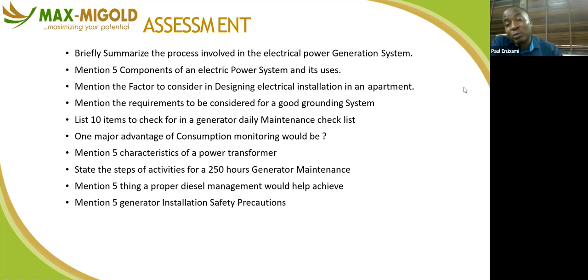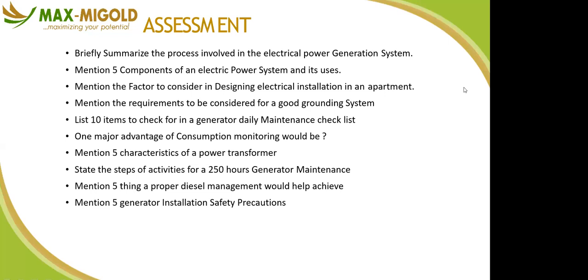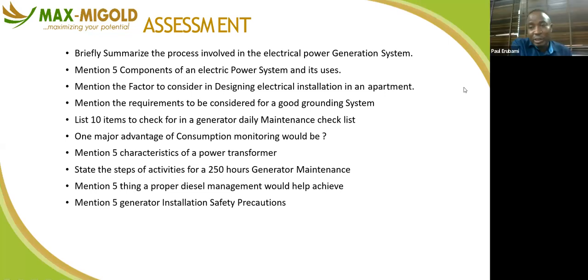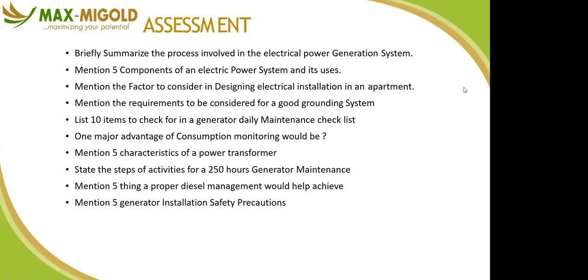There are other facilities that you are not putting to use, maybe your conference room or some AC or some room. So when you are doing load analysis, you do the total load of the installed facility, assuming that those facilities are in use at all times. That's one. Then you do your current load demand as well, like the record you are taking when the generators are working, like the ladies that shared 90 kilowatts and 200 kilowatts. Because they have a record to show, this is what we are currently consuming.